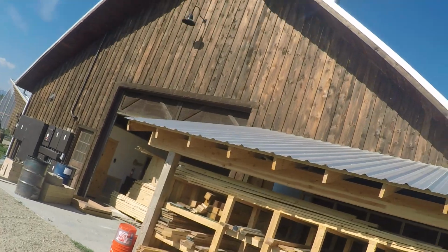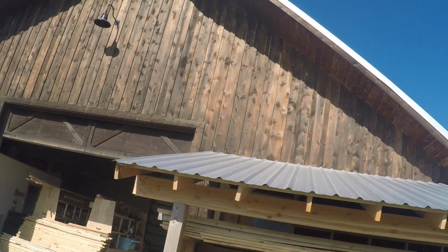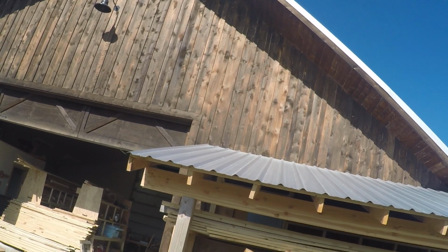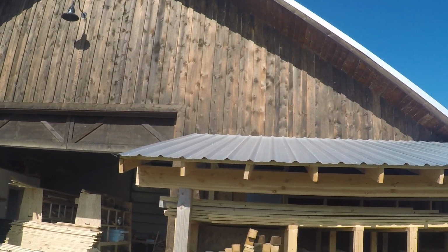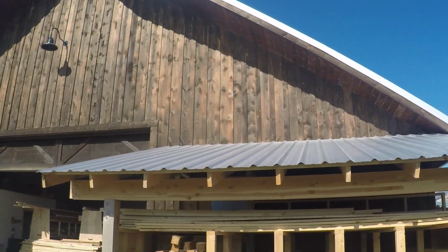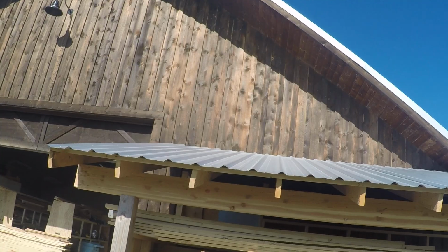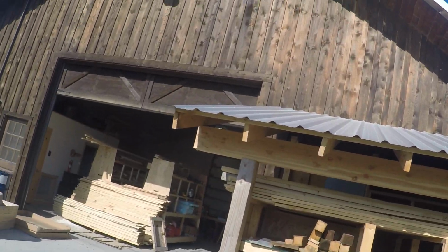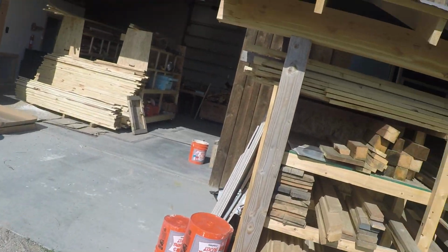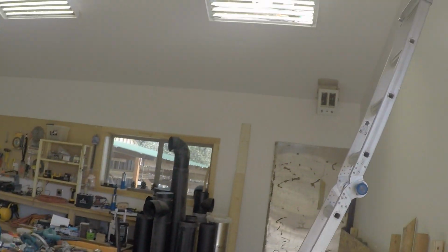It's not stainless, it's galvanized. So hopefully it's mated properly to the same brand or close enough size. They'll work okay together. But it could be that the galvanized one won't run the gases or the moisture. If there gets condensation, if they don't match properly, it could get inside the pipes, and then it gets your insulation wet inside the pipes, and then it's not insulated.